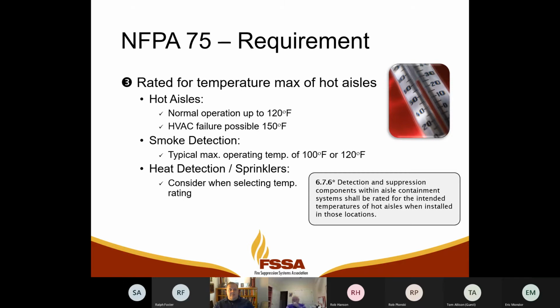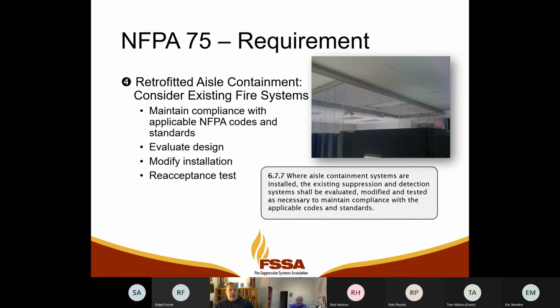It's possible to get so hot in those rooms that we may fuse the sprinklers. So it's just, again, something else that we need to think about, and this is part of the code that addresses it. Number 4, a retrofitted aisle containment. When you retrofit aisle containment, the code says you need to consider existing fire systems. So it's kind of like a retroactive thing. You need to go back and address the existing systems when you're putting in aisle containment.